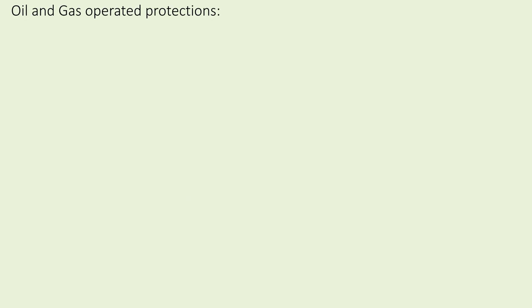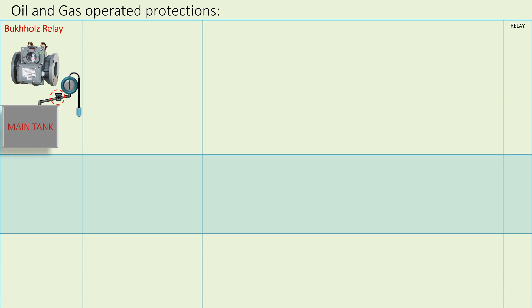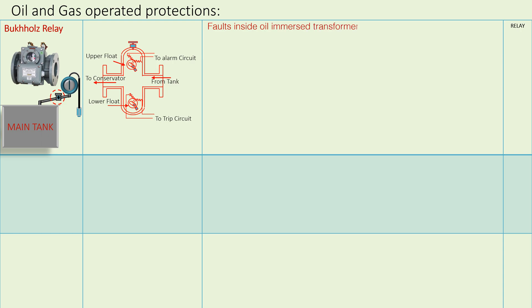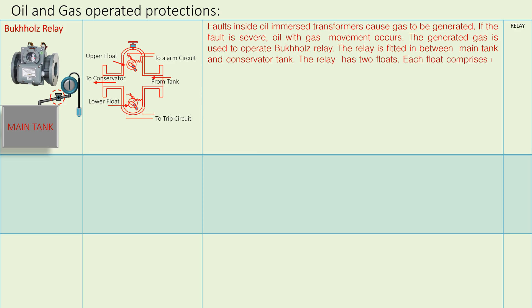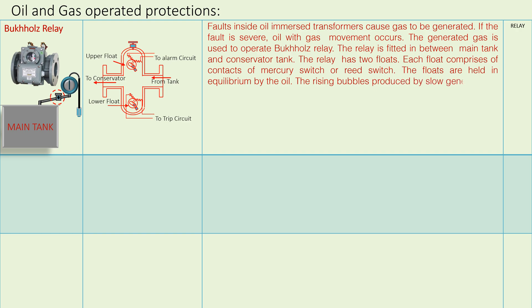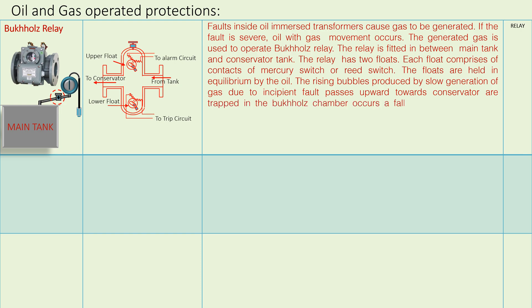Oil and gas operated protection — Buchholz Relay. Faults inside oil-immersed transformers cause gas to be generated; if the fault is severe, oil with gas movement occurs. The generated gas is used to operate the Buchholz Relay. The relay is fitted between the main tank and conservator tank by suitable pipes. The relay has two floats; each float comprises contacts of a mercury switch or reed switch. The floats are held in equilibrium by the oil. Rising bubbles produced by slow generation of gas due to an incipient fault pass upward towards the conservator or are trapped in the Buchholz chamber, causing a fall of oil level inside the chamber.